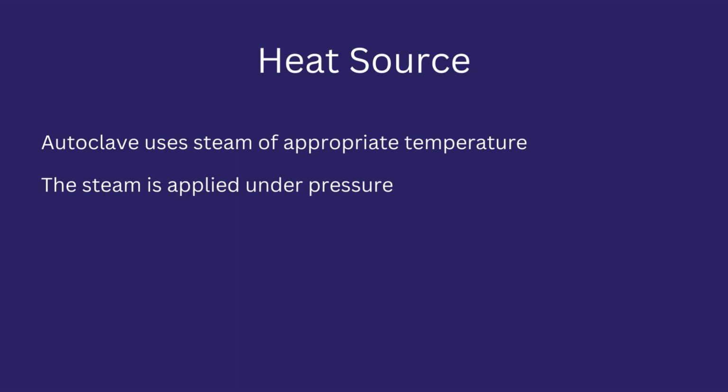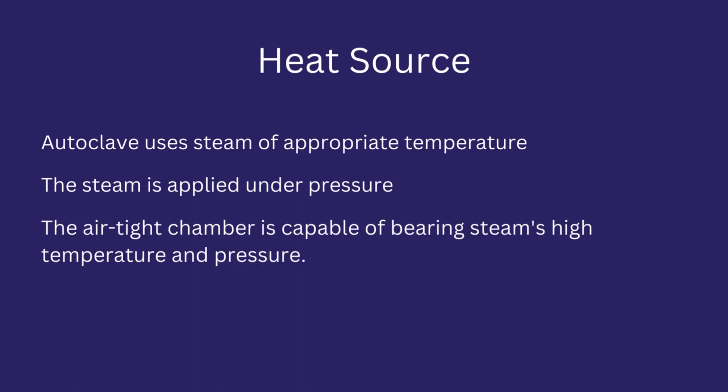Steam is injected inside the chamber with high pressure, and the high pressure assists in achieving the desired temperature. Because the temperature of steam is 100 degrees centigrade, and to achieve a temperature above 100 degrees centigrade, its pressure needs to be increased. And this is according to various chemical laws. Since the steam is applied with pressure, the chamber must be airtight and capable of bearing high pressure. Otherwise, the chamber will explode and cause destruction.